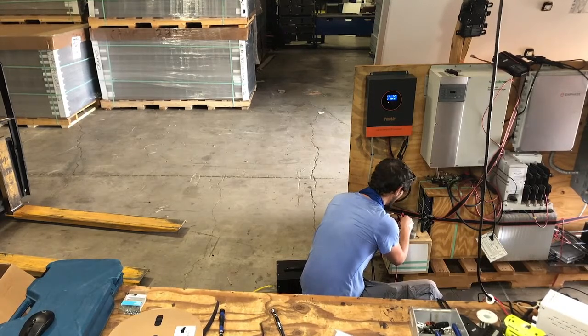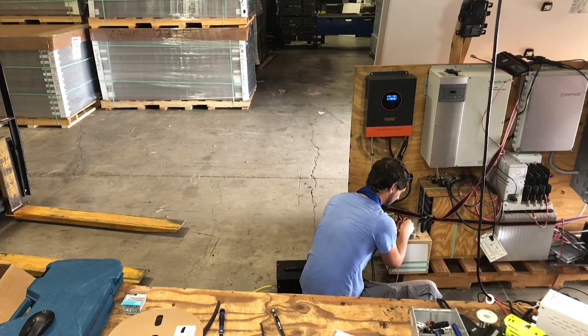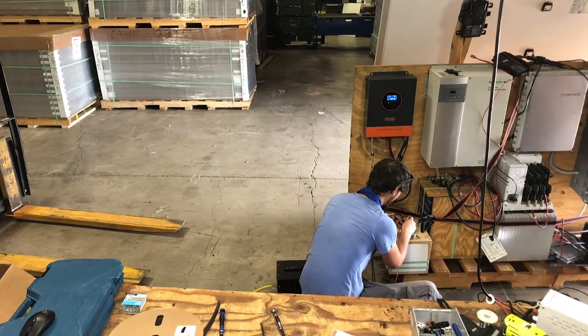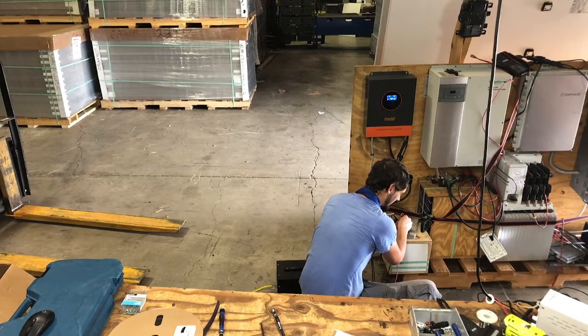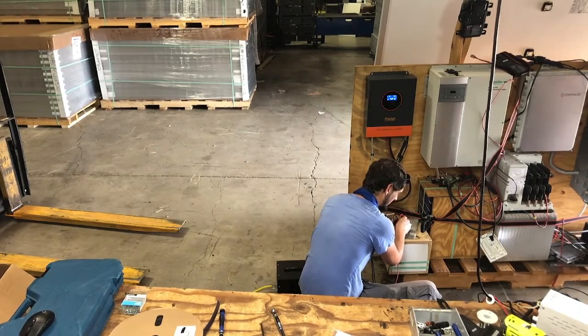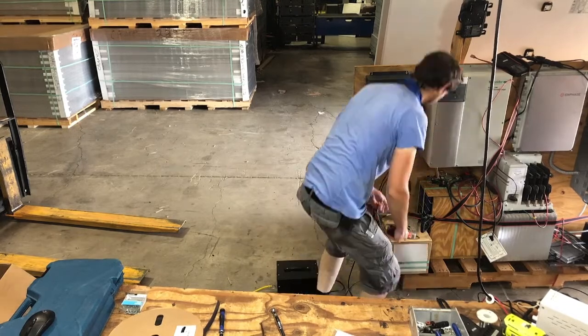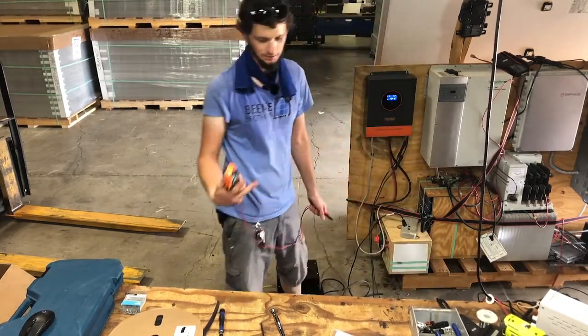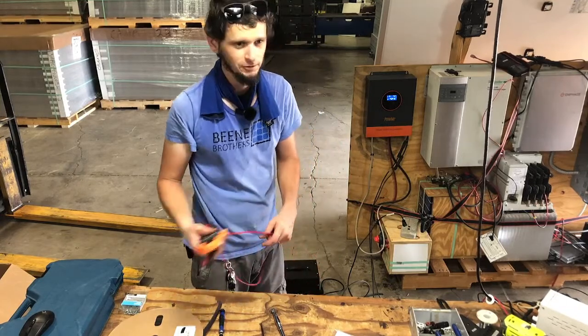So I have 120 volts between neutral and line, but then line to ground is 57 volts, and ground to neutral is 63 volts. So I really need to bond, I need to connect neutral and ground together, if you can even hear me.